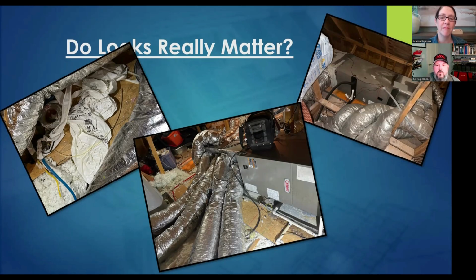Is the ductwork sized properly? When we're specifically focusing on duct here, if my system looks like this when the guys are done, I can make a pretty accurate assumption that this stuff is not designed properly, it's not flowing, nothing was done properly here. It's likely the cheapest bidder got the job, so keep that in mind. You have a huge role to play here. It's kind of a catch-22 because don't go with the cheapest bidder - however, a lot of these bigger companies will be the most expensive and you'll still get a cheap job out of them. So you have to be really careful.